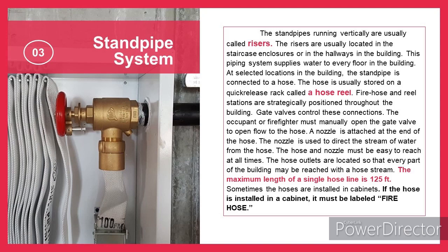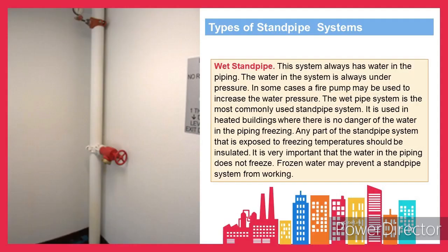The hose and nozzle must be easy to reach at all times. The hose outlets are located so that every part of the building may be reached with a hose stream. The maximum length of a single hose line is 125 feet. Sometimes the hoses are installed in cabinets. If the hose is installed in a cabinet, it must be labeled fire hose. Here are the types of standpipe systems.